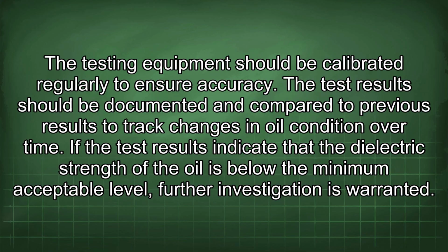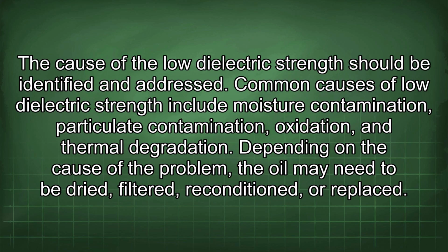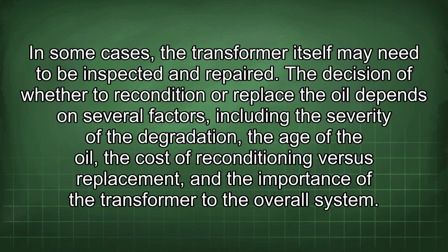If the test results indicate that the dielectric strength of the oil is below the minimum acceptable level, further investigation is warranted. The cause of the low dielectric strength should be identified and addressed. Common causes of low dielectric strength include moisture contamination, particulate contamination, oxidation, and thermal degradation. Depending on the cause of the problem, the oil may need to be dried, filtered, reconditioned, or replaced. In some cases, the transformer itself may need to be inspected and repaired.